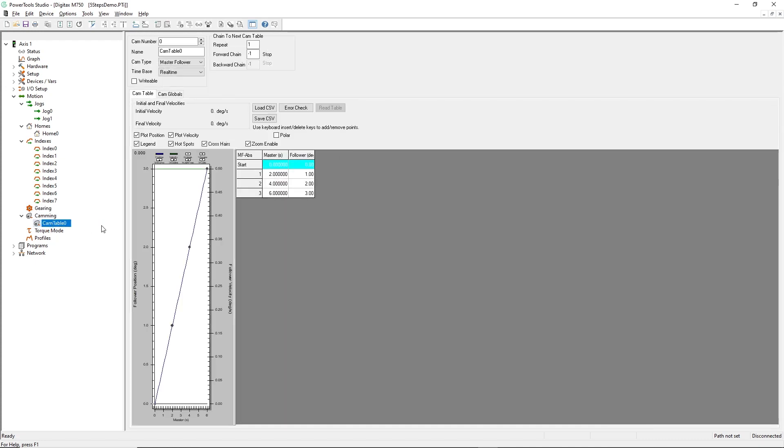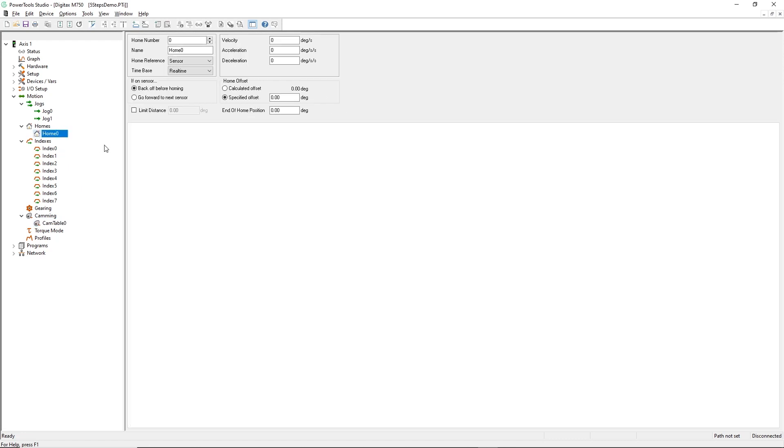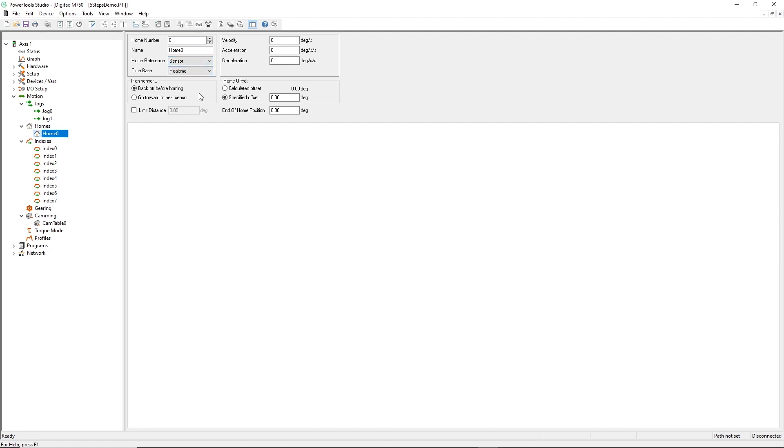I'll start by defining my homing routine. This is the home configuration. I'll elect to use the proximity sensor that I assigned to drive input 4 in the previous step as my home reference. I may also choose what action to take if the proximity flag is active when I start my home profile here. Now I'll set my homing speed, acceleration, and deceleration.